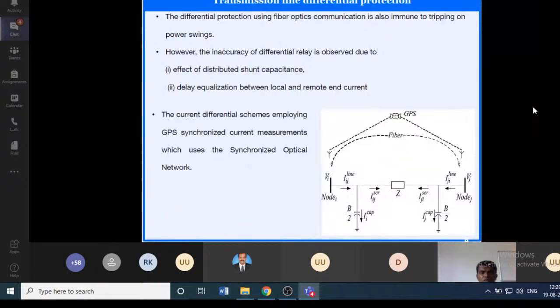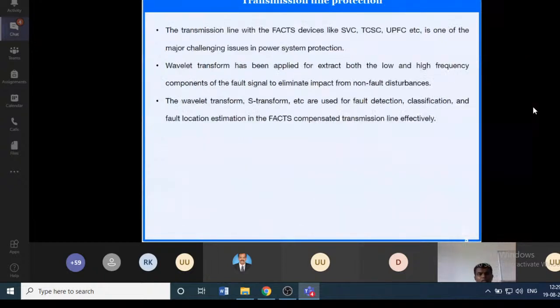This problem can be solved using the PMU measurement. The PMU will get the information of the current signal and time stamp it with the GPS clock, and that will be transmitted through the fiber optics. Then we can compare the current signals at the two ends corresponding to the GPS time. Additionally, a transmission line with FACTS devices like SVC, TCSC, UPFC is going to give more challenges for power system protection, since it adds other components inside the transmission line that will confuse the protection device.